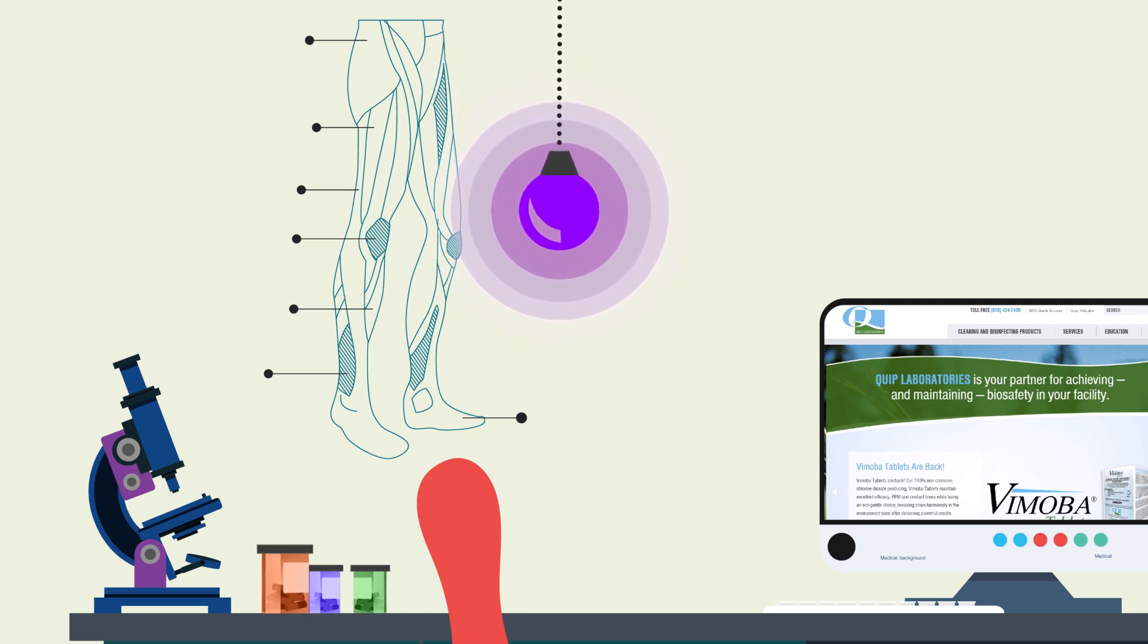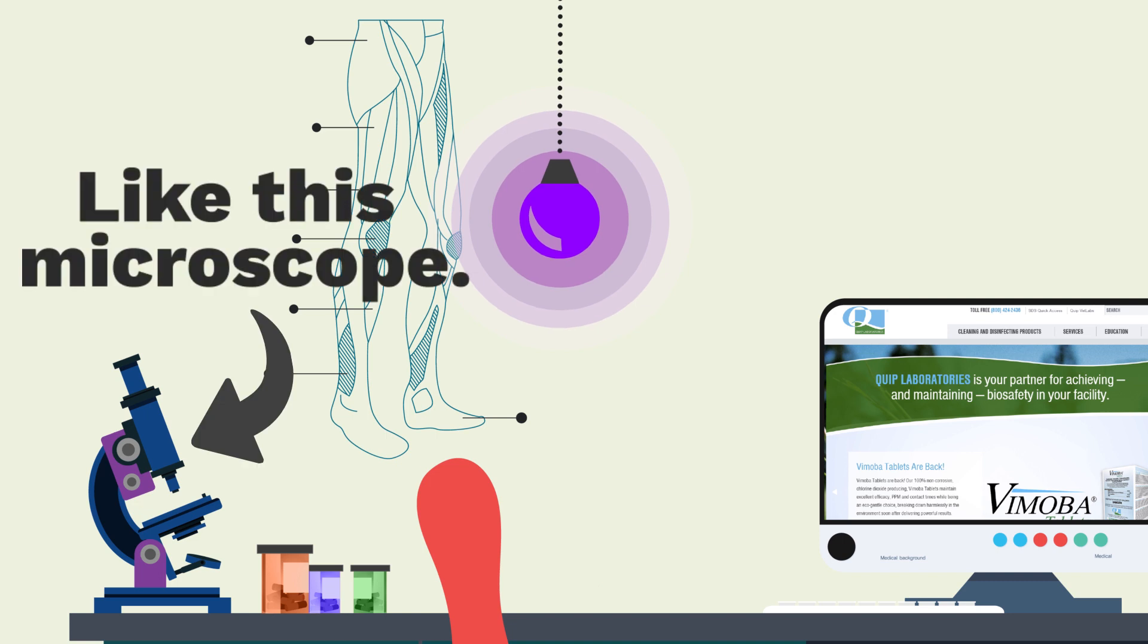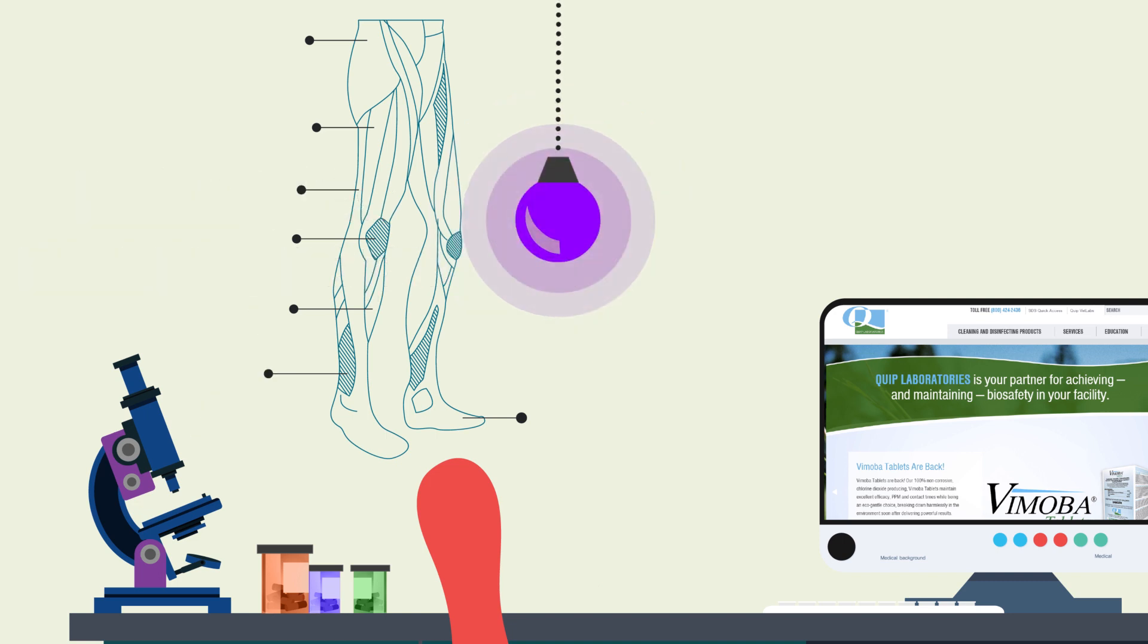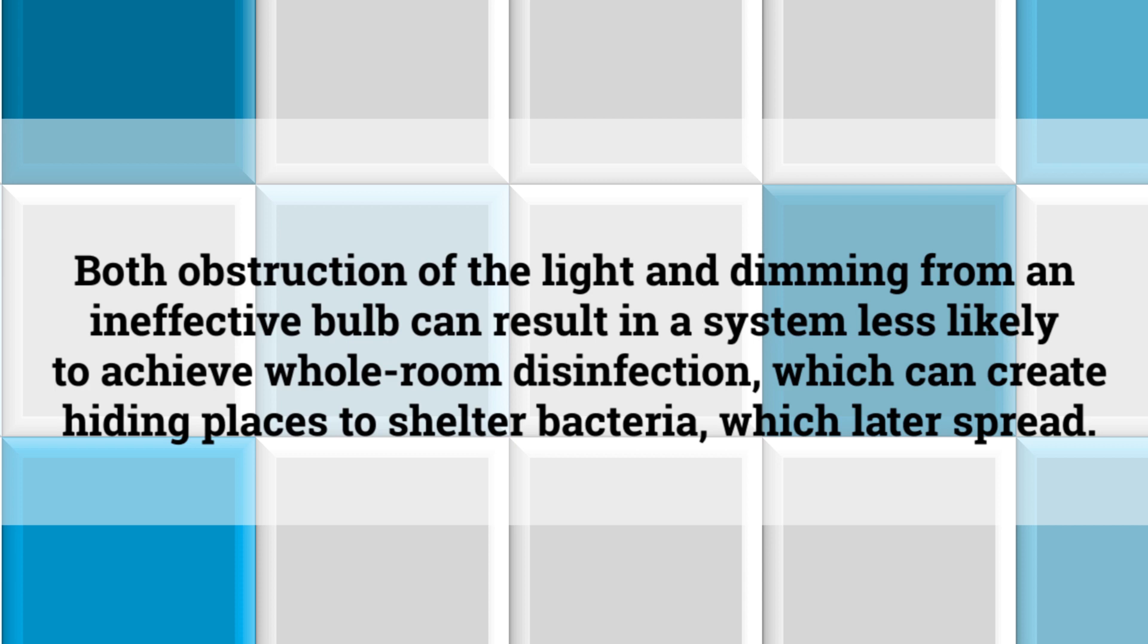See, UV efficacy can dip because of obstruction, something in between the light and the intended surface, or dimming, the UV bulb not operating at full capacity. Both obstruction of the light and dimming from an ineffective bulb can result in a system less likely to achieve a whole room disinfection.